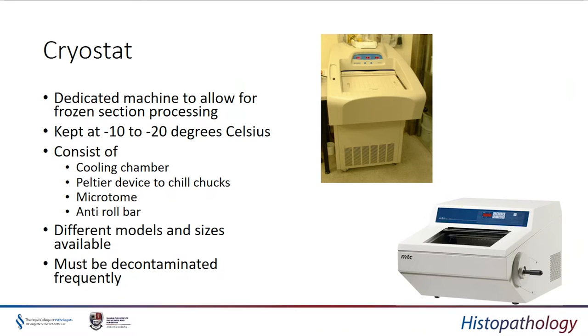The key piece of equipment for a frozen section is a cryostat — a dedicated machine which allows frozen section processing. It must be kept at minus 10 to minus 20 degrees Celsius. It consists of a cooling chamber which allows the tissue to cool, a Peltier device which can be used to chill the chucks on which tissue is processed, a microtome for tissue sectioning, and an anti-roll bar and tissue sectioning area which allows you to extract the tissue section onto a glass slide for staining and examination. There are many different types and models available, with numerous videos on YouTube and commercial websites.